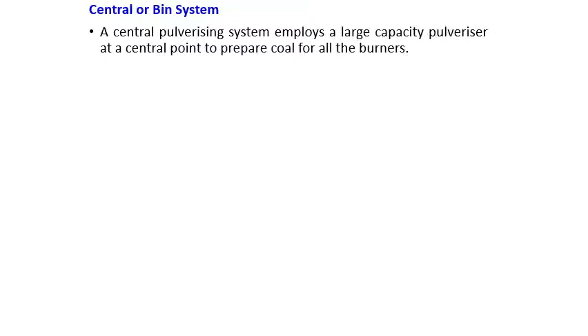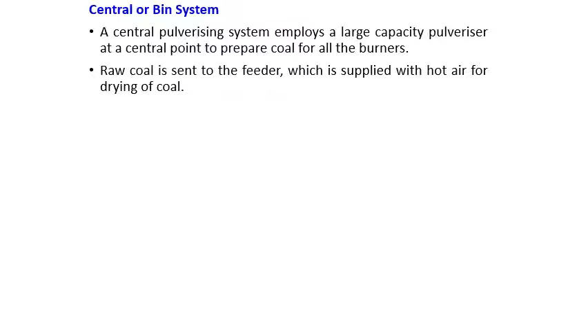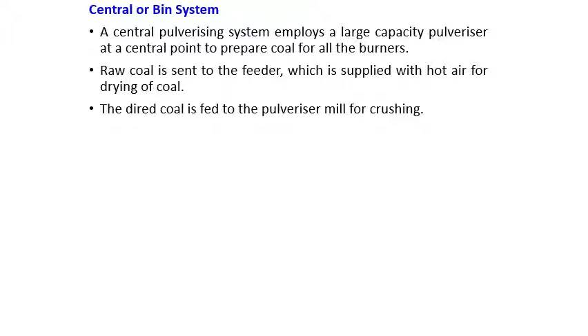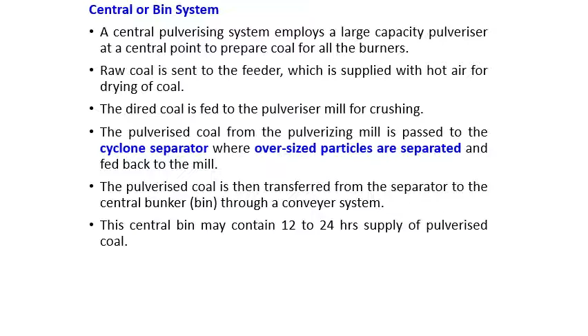So in the central or bin system, the central pulverizing system employs a larger pulverizing capacity to prepare coal for all burners. Raw coal is sent to the feeder, which is supplied with hot air for drying the coal. The dried coal is fed to the pulverizer mill for crushing. The pulverized coal from the mill is passed to the cyclone separator. In the cyclone separator, because of the centrifugal action, the sizes get separated. The bigger size coal is fed back to the mill. The pulverized coal is then transferred from the separator to the central bunker, that is the bin, through the conveyor system. The central bin may contain a 12 to 24 hour supply of pulverized coal.